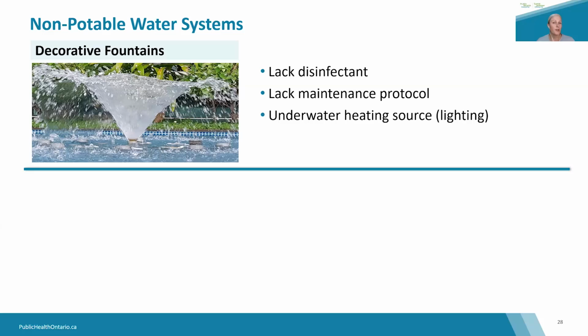They may also have underwater lighting, which can create a source of heat, which would allow for warmer water temperatures, which would then be ideal for Legionella. They often produce aerosols, so if Legionella bacteria enters the system, it can be dispersed in the air, and there have been cases associated with fountains. The CDC recommends not having a decorative fountain in areas with high-risk individuals, such as long-term care homes or hospitals, as they're not considered to be necessary, and they do present a Legionella risk if they're not maintained properly.